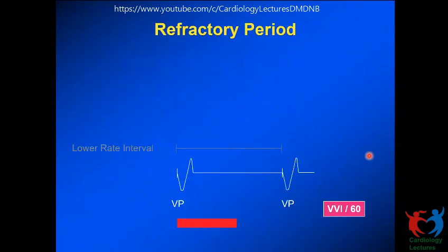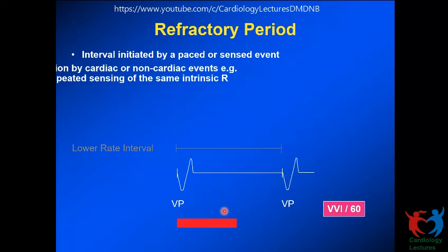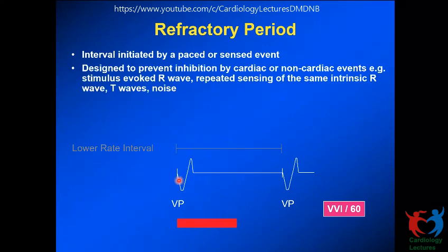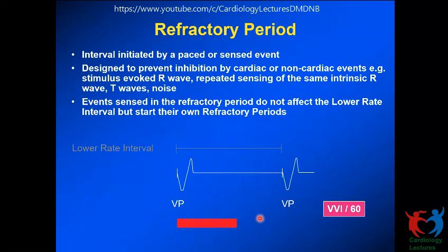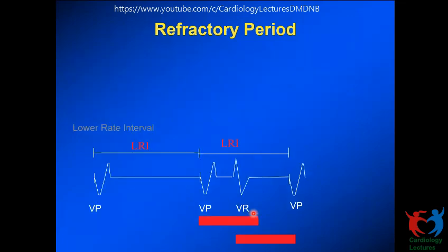So we want to put some restriction, and that's where the refractory period and the blanking period come into play. On delivering a V pace, there is a programmable interval, which is the refractory period, during which, if the pacemaker senses, it will ignore that sensing. After a paced event or a sensed event, we don't want to sense the same QRS one more time or the T wave. In order to ignore that sensing, we have the refractory period. Usually it's a programmable period, typically about 300 milliseconds in a ventricular single chamber pacemaker. And if there is sensing happening, the pacemaker will call it a refractory ventricular sense, and it will ignore it and will not reset the clock, like in this case.